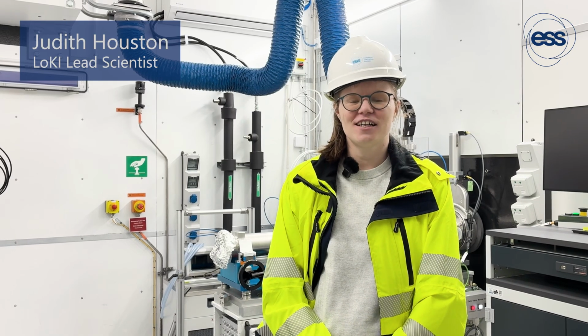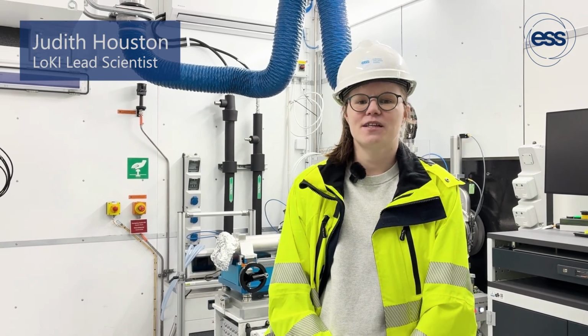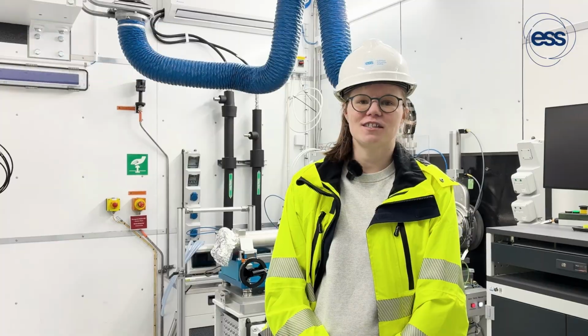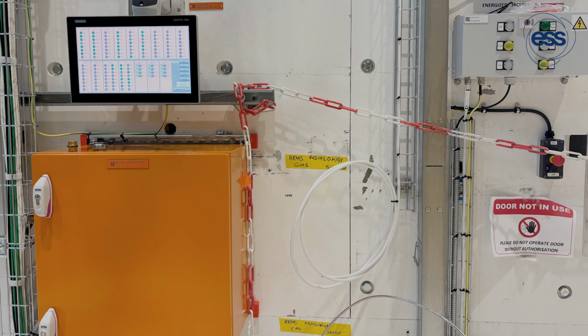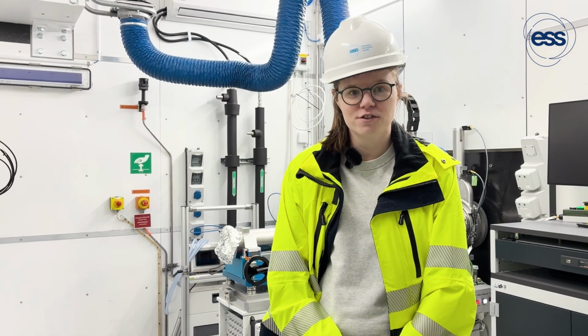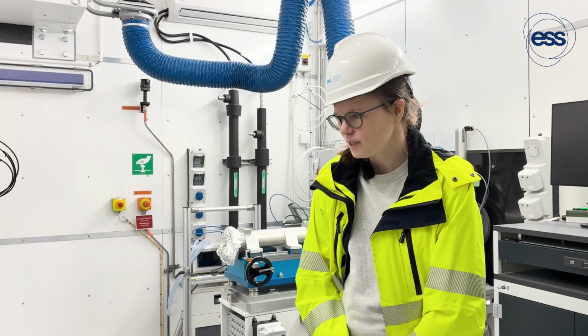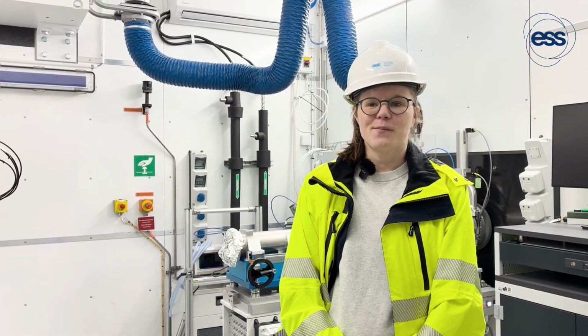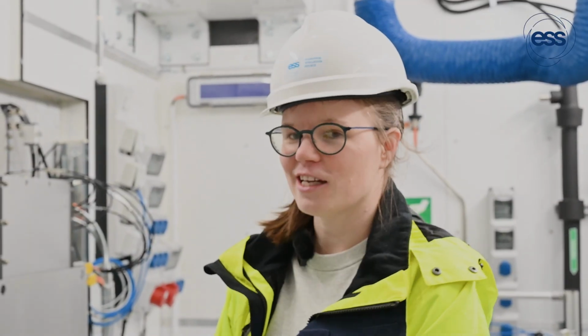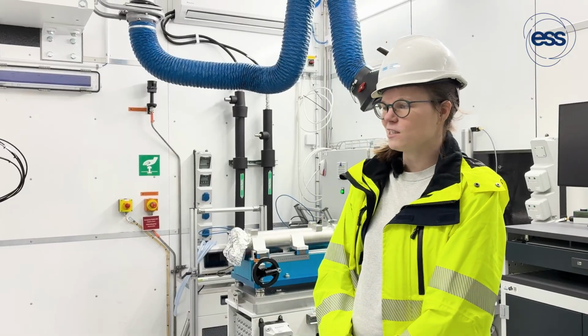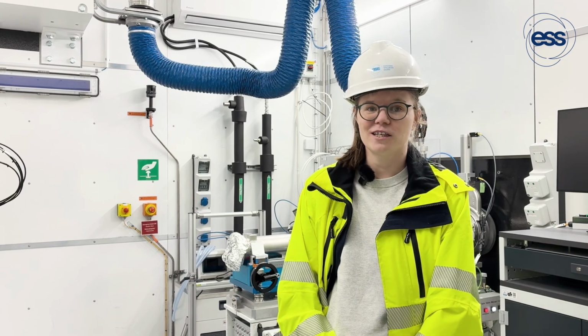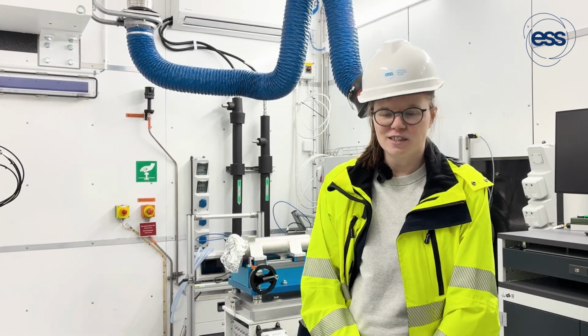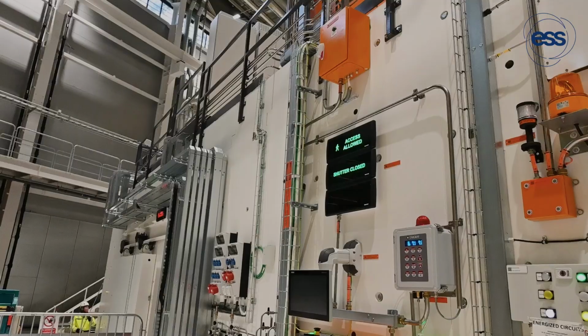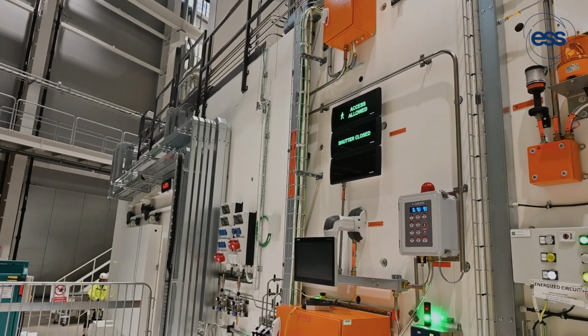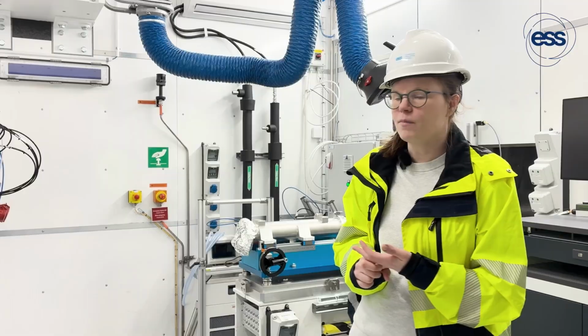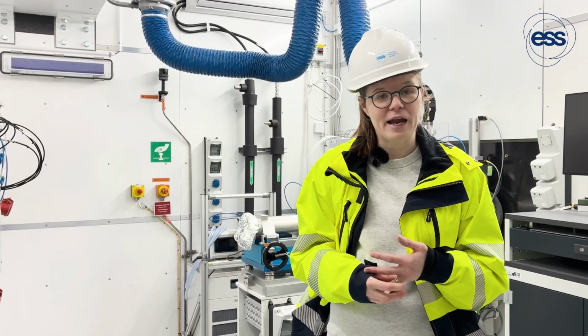Our ISSR is essentially done now, so that means that we've passed, the instrument is constructed, the safety features are all installed and tested, and if we were to get neutrons tomorrow, we'd essentially be good to go. That's an excellent milestone for us, but that technically doesn't mean that the setting up of the instrument is over. So for this next period, until ESS starts online, we'll be fine-tuning, developing things like the instrument control software, which works, but there's a lot we can add to it to make it easier to perform and easier for users. But actually a large portion of our work will really just be preparing for hot commissioning.